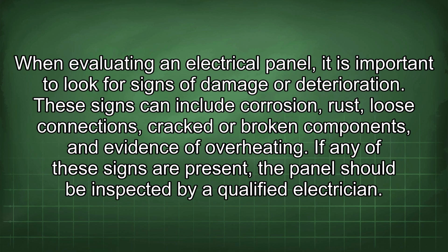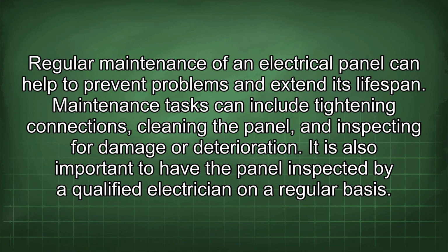When evaluating an electrical panel, it is important to look for signs of damage or deterioration. These signs can include corrosion, rust, loose connections, cracked or broken components, and evidence of overheating. If any of these signs are present, the panel should be inspected by a qualified electrician. Regular maintenance of an electrical panel can help to prevent problems and extend its lifespan. Maintenance tasks can include tightening connections, cleaning the panel, and inspecting for damage or deterioration. It is also important to have the panel inspected by a qualified electrician on a regular basis.